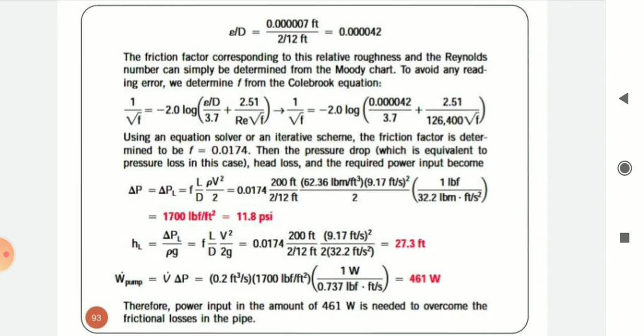Putting those values, we get delta P = 11.8 psi. So head loss = delta PL / (rho g) = f (L/D) (V²/2g). Putting those values, we get 27.3 ft head loss. For the water power requirement, we get V dot times delta P = 461 W. Therefore, power input in the amount of 461 watts is needed to overcome the frictional losses in the pipe.